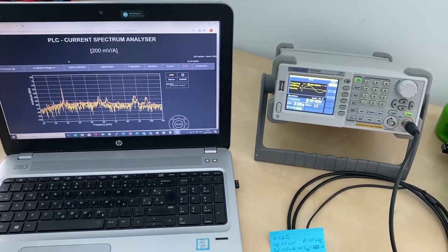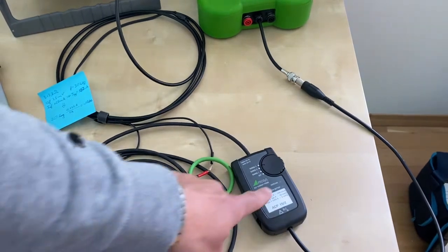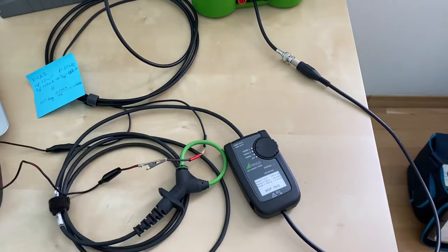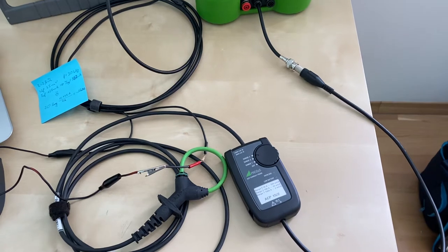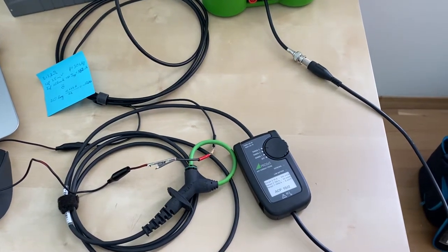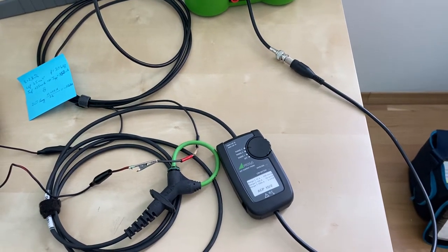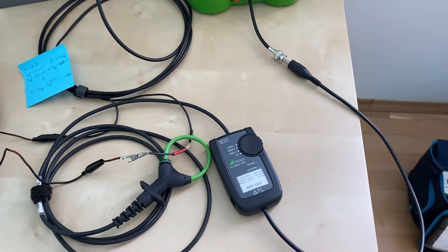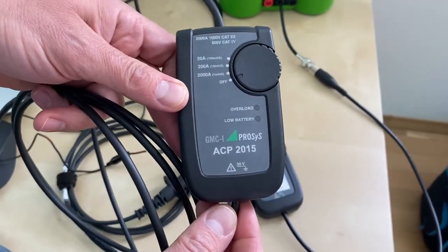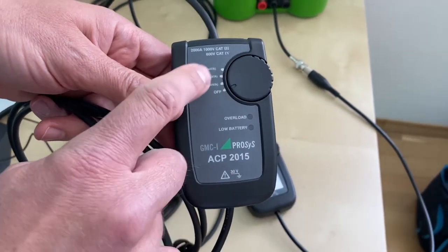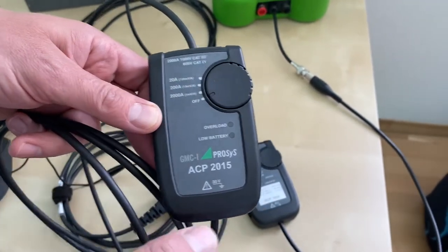Now, please let's turn attention to the Rogowski coil again. The question was whether this adapted version with the more sensitive output is better or not. The answer would be it's better, but only when measuring very, very small currents. It's impossible to say what types of currents utilities will be using here, but both can be used. The other one that was provided, this one over here, is also good. The only drawback is that it cannot measure such small currents. Now the question is whether they will be measuring such small currents or not.